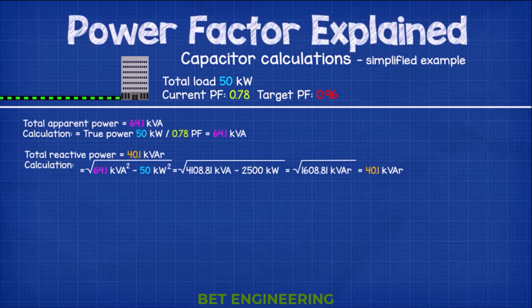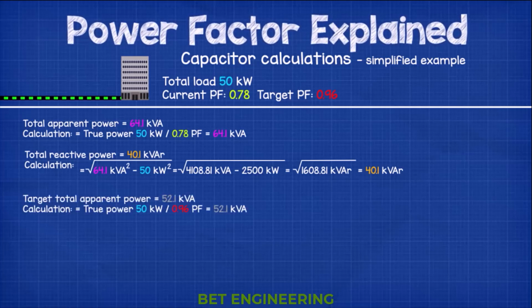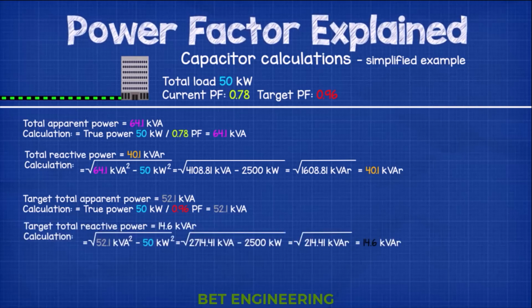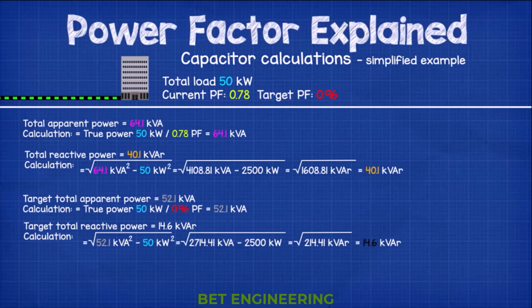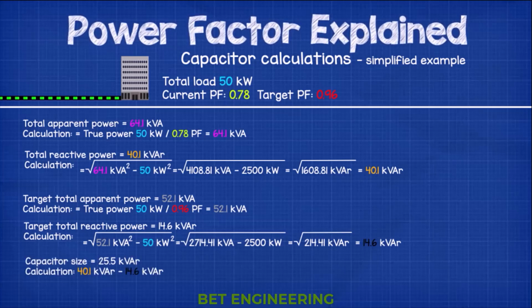It also has a reactive power of 40.1 kVAR. We find that by taking the square root of the kVA squared minus the kilowatt squared. So take the square root of 64.1 squared minus 50 kilowatt squared. Then we calculate what the value should be if we had a power factor of 0.96. So our apparent power should be 52.1 kVA. We find that from 50 kilowatts divided by 0.96 power factor. Then we find our reactive power, which is the square root of the kVA squared minus the kilowatt squared. So the square root of 52.1 kVA squared minus 50 kilowatt squared, which gives us 14.6 kVAR. The capacitor therefore needs to make up the difference between these, so 40.1 kVAR minus 14.6 kVAR, which equals a 25.5 kVAR capacitor.